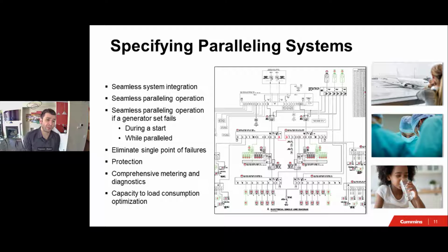Seamless paralleling operation if a generator set fails during a start or while paralleled. If we have 5 gensets paralleled and genset number 3 decided to go out to lunch that day, we don't want that entire fleet of gensets to stop working because that genset is not happy that day. We want to eliminate single point of failure, and then we need to have some level of protection, and we need to have a comprehensive level of metering and diagnostics.